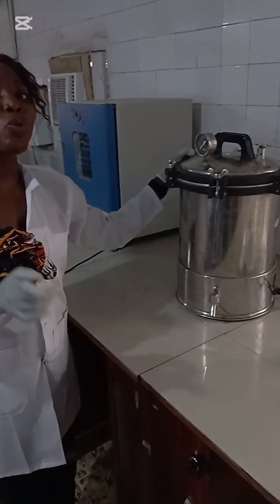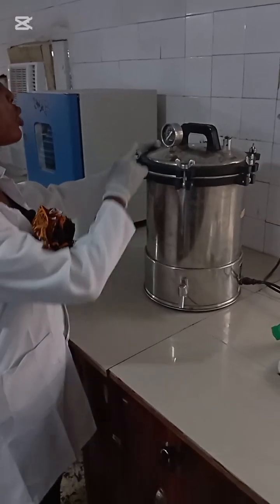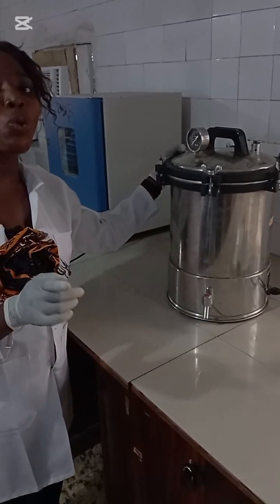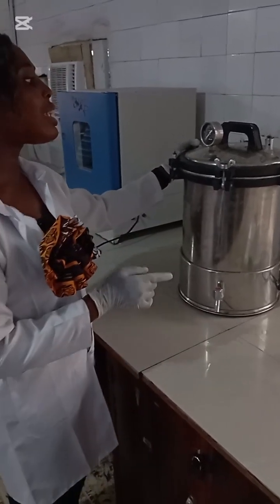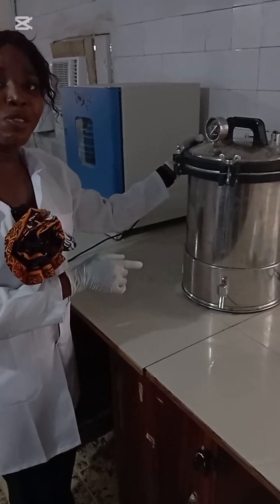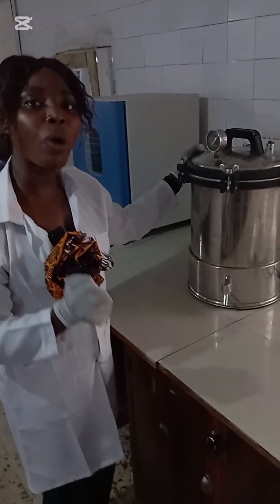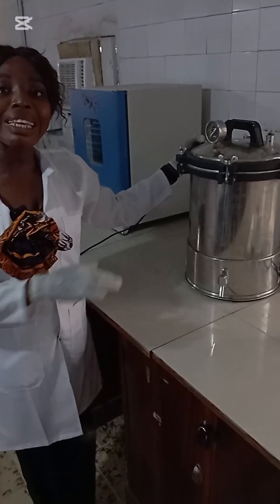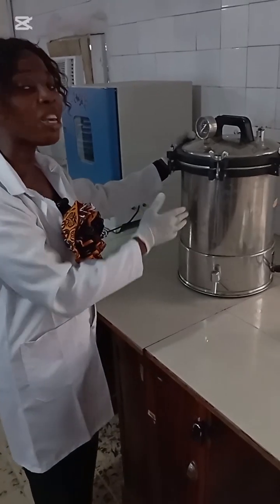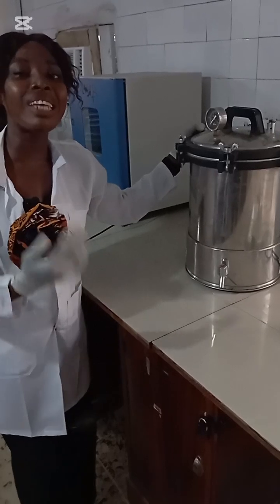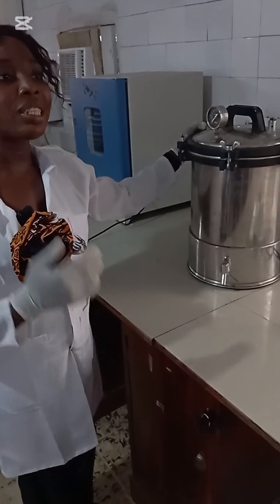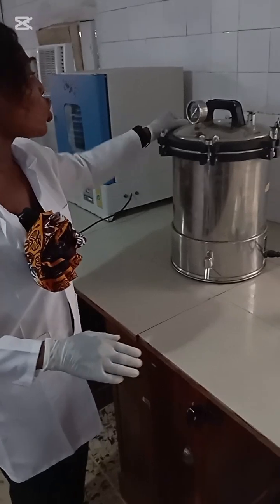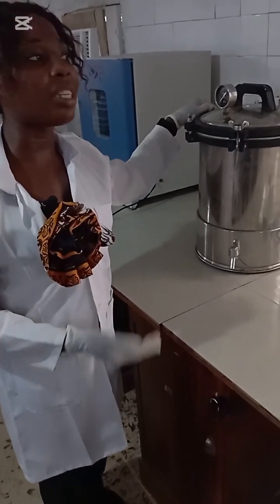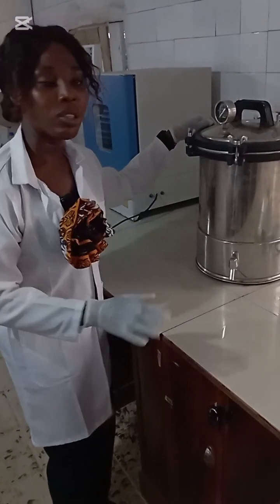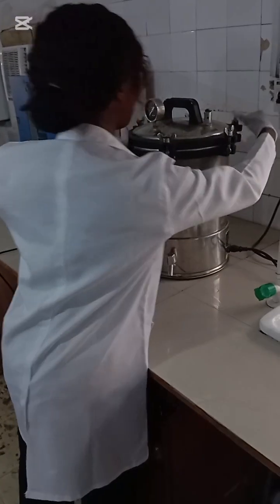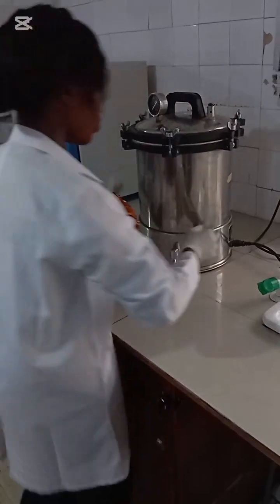So we need the pressure to be at 15 psi for the temperature to rise up to 121 degrees Celsius to produce steam that will penetrate the elements for sterilization, to cause coagulation of bacterial proteins that kill the bacterial organisms or any organism if present, because we want to produce a sterile culture media. I told you earlier that these things are done in aseptic procedure. So whatever organism is there in our medium, by any chance, we want to kill all of them, because we don't want to see growth and think that it's from our patient when actually it's from our culture media. So we have to sterilize it.